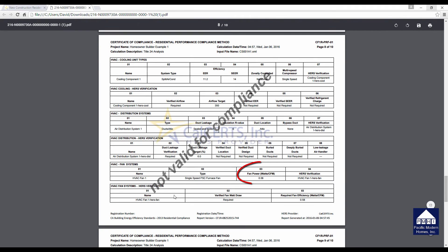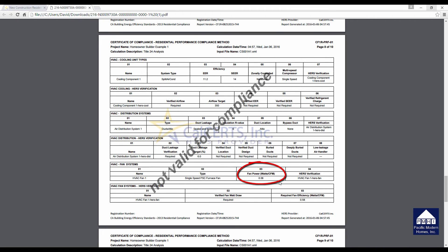So if you have a 5-ton air conditioner, that's 60,000 BTUs. What we're looking for here is to make sure that the ducts are not kinked, that they're put in efficiently, and your house will pass if that's done correctly. Insulation on the ductwork has to be R6. That's pretty standard. In some cases, some areas, that will be R8. The ducts are located in the attic, and a penalty for having the ducts in the attic has been taken into the energy calculations. You have also down here, how much leakage can you have on your ductwork? 6% is the standard. You'll get down into the fan efficiency. The fan can use no more than 0.58 watts per CFM.